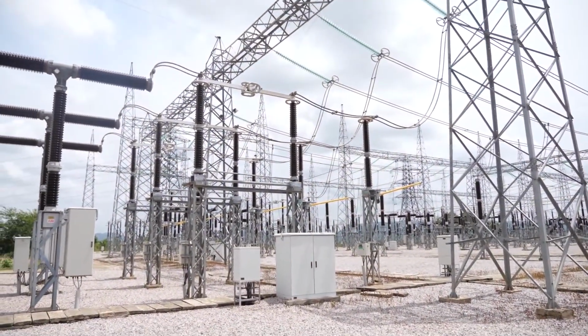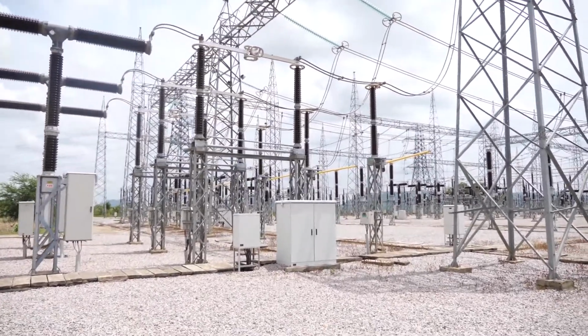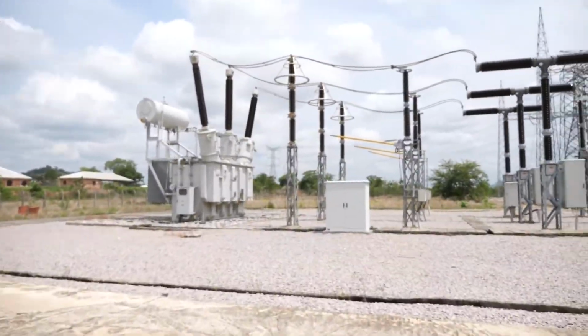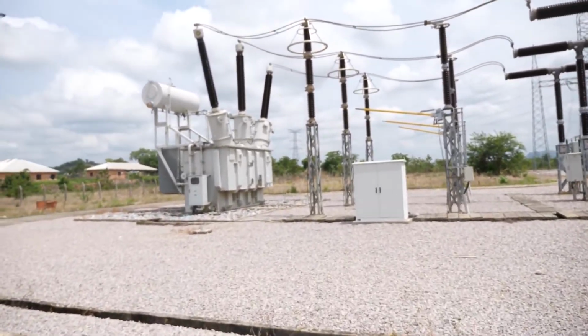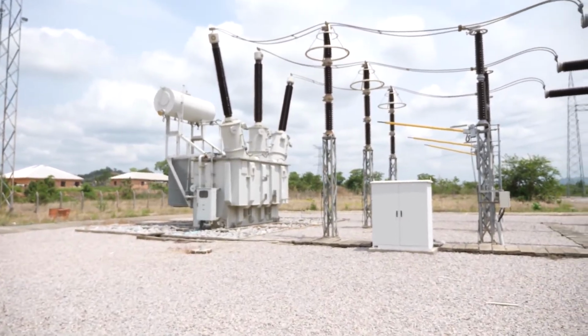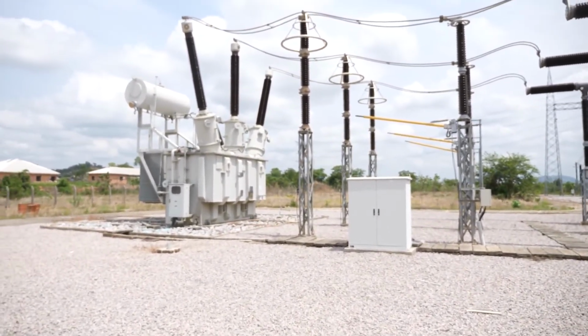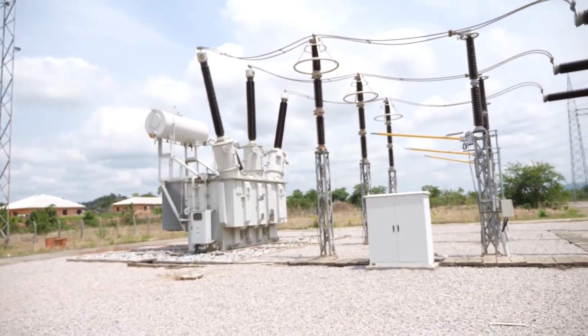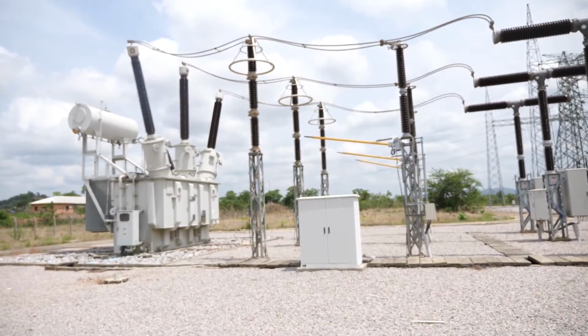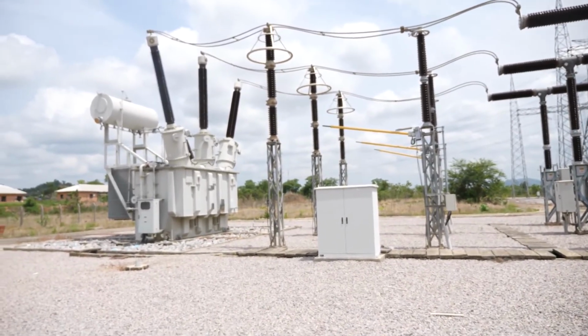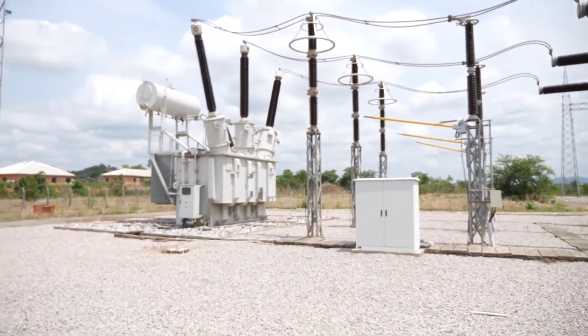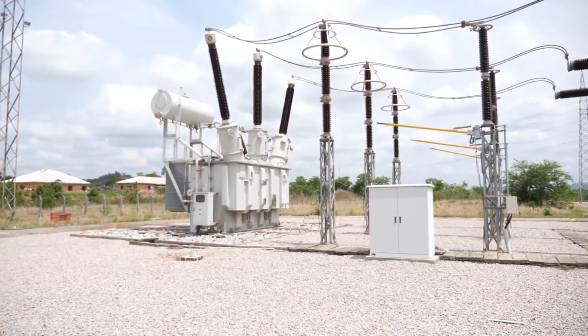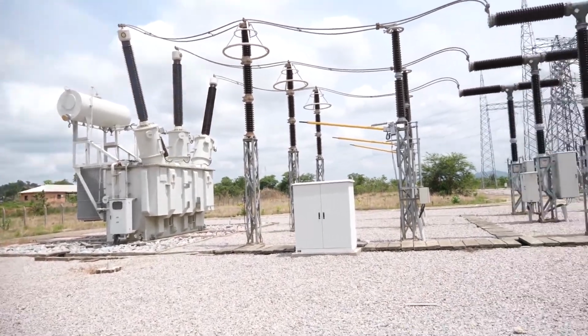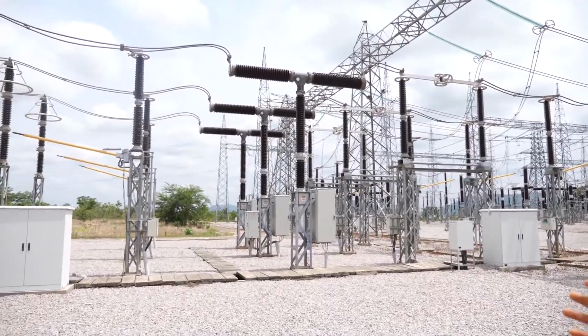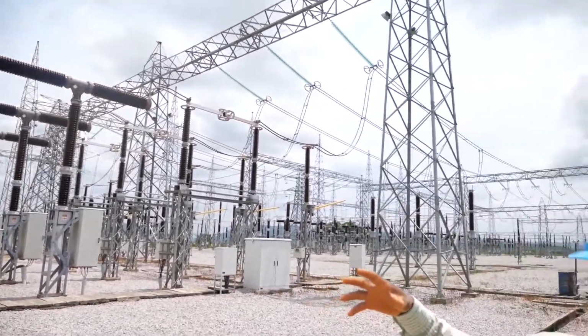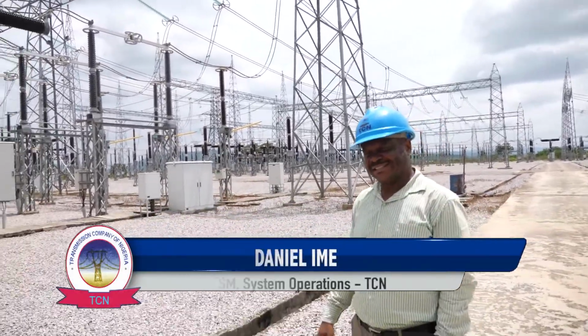You are right with Engineer Ime, the substation supervisor at the switchyard of the Lokoja transmission substation. This is a 75 MVAR shunt reactor. The work of the reactor is to suppress the voltage. Normally, this station has been experiencing very high voltage, and to cope with that, we installed a reactor. So this is the reactor. The reactor is tied to bus bar 1, and there's a link between bus 1 and bus 2. Those two buses are tied. So the effect of the reactor is felt on both buses.